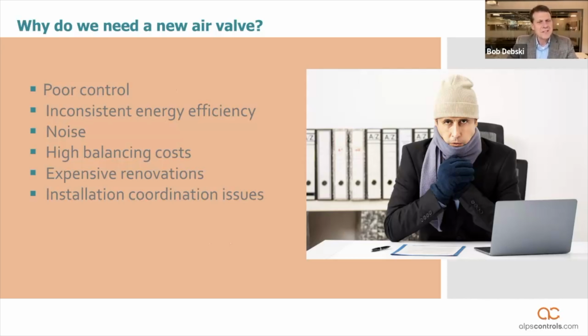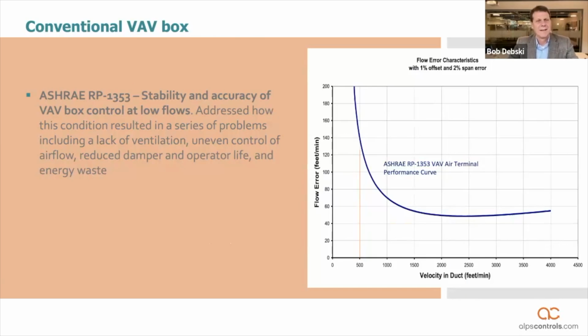So what's interesting here is this is an opportunity to change this, to address these issues and provide a better product. Even ASHRAE recognized that there's a problem with VAV boxes. About 10 years ago, ASHRAE sponsored a research project, 1353, that looked at some of these problems and tried to determine what was causing this.